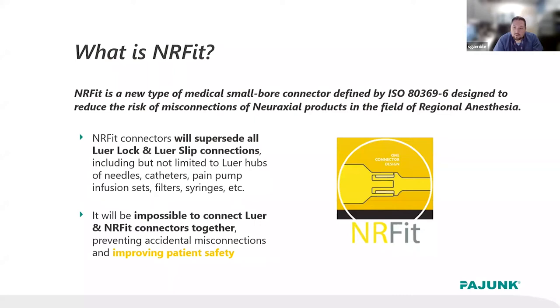NRFit, for those of you who do not know already, is a new type of medical small bore connector that was defined by the ISO 80369-6 and was designed to reduce the risk of misconnections of neuroaxial products in the field of regional anesthesia. Misconnections, as you can imagine, are quite dangerous in the medical field and can sometimes lead to even fatal outcomes. Because facilities and various departments all use the same Luer connectors, you can see how this can become dangerous. And administering the wrong medication into the wrong tubing or connection has happened in the past, and it's still happening today. NRFit is meant to create its own connector for neuroaxial and regional anesthesia connections.